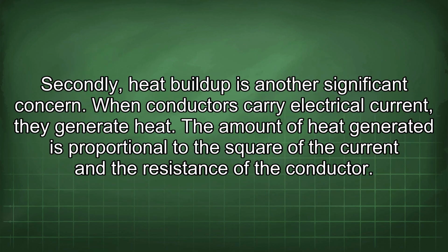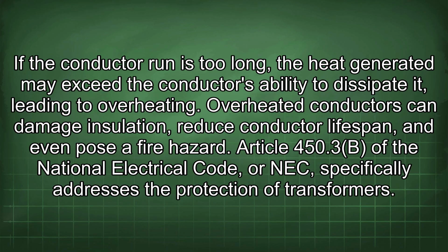Secondly, heat buildup is another significant concern. When conductors carry electrical current, they generate heat. The amount of heat generated is proportional to the square of the current and the resistance of the conductor. If the conductor run is too long, the heat generated may exceed the conductor's ability to dissipate it, leading to overheating. Overheated conductors can damage insulation, reduce conductor lifespan, and even pose a fire hazard.